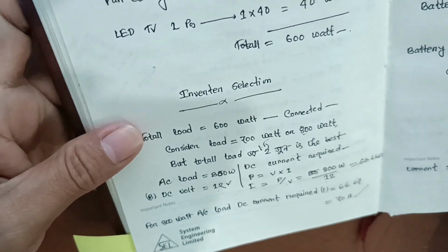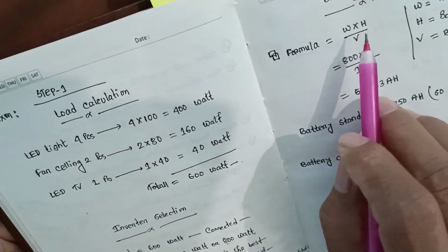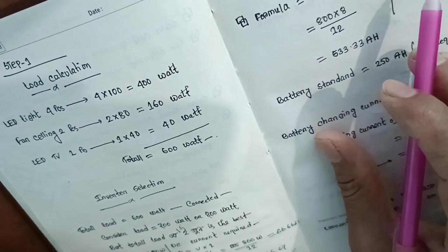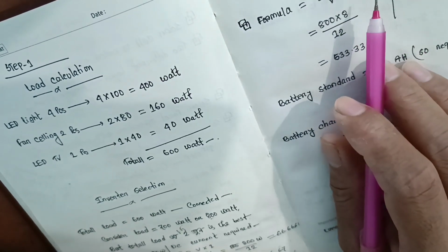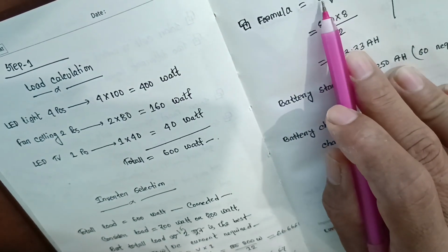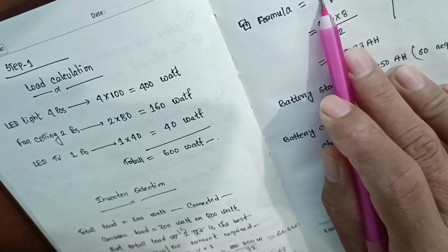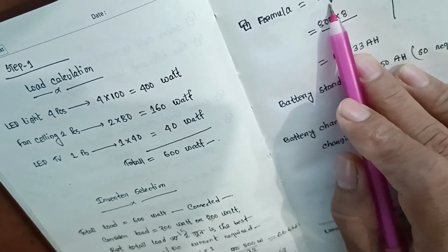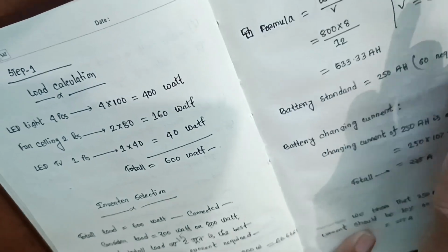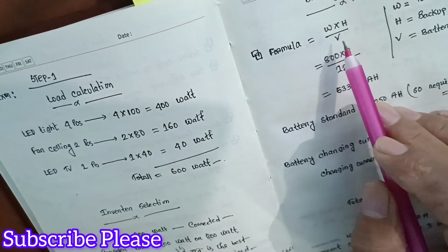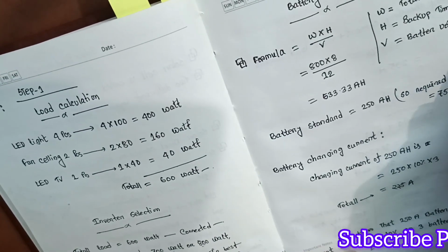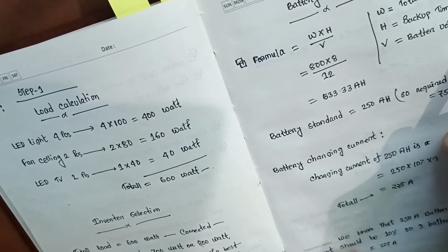Okay. Now the battery selection, the third step of this project. The formula is watt into hour divided by voltage. W is the total load of 800 watts, the backup time is 8 hours, and V is the battery voltage of 12 volts.